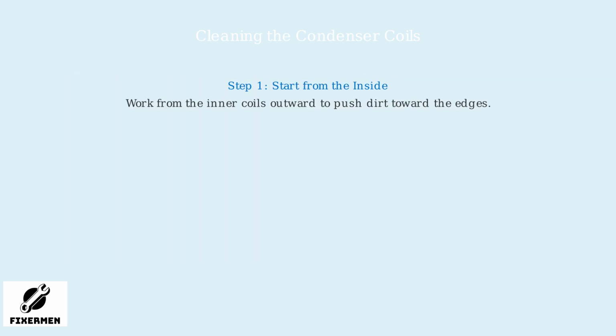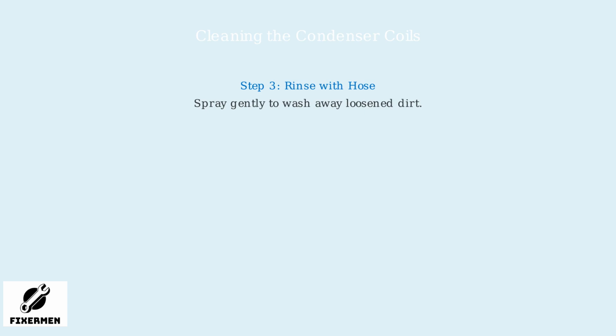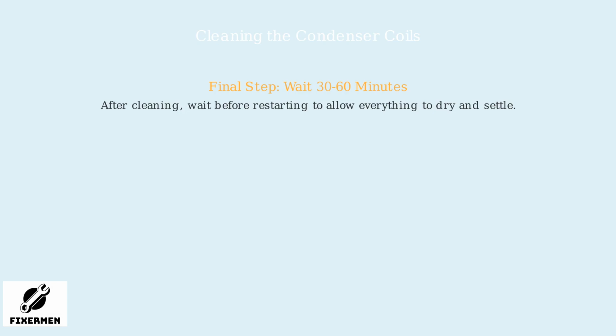Start cleaning from the inside of the unit and work your way out, gently removing dirt and debris that restricts airflow. Use the fin comb to gently comb through the fins, removing buildup without bending or damaging them. Follow up with a gentle hose spray to rinse away the dirt and debris you've loosened. Cleaning removes dirt that blocks airflow, as shown in this before and after comparison. After cleaning, wait 30 to 60 minutes before restarting the unit to let everything dry and settle properly.